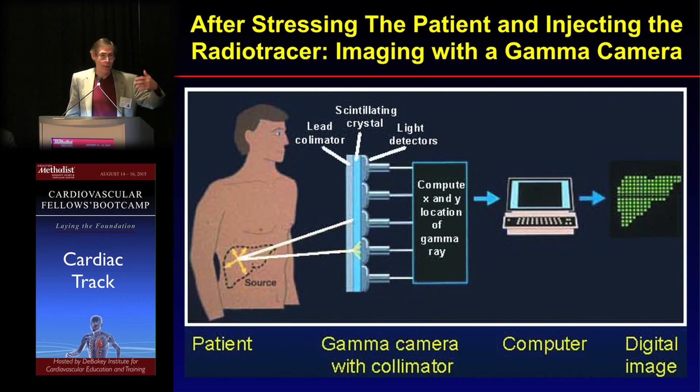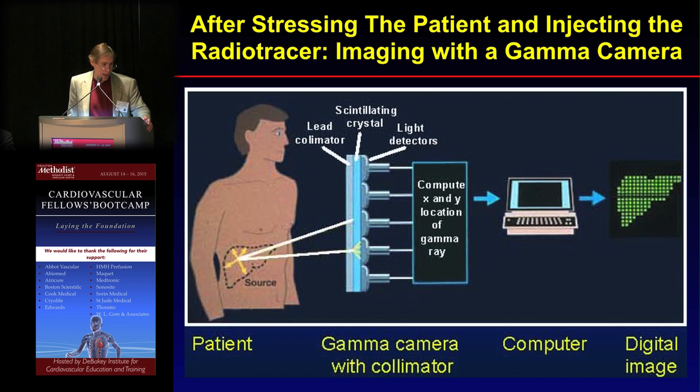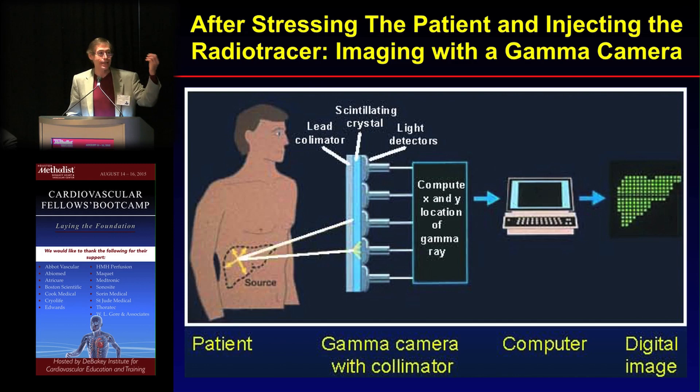Once we stress the patient and inject the radiopharmaceutical, we have to image that patient. Because gamma rays can get out of the body, they hit a lead collimator so that only photons parallel to the organ being imaged enter the sodium iodide crystal. When the photon hits the crystal, it causes a scintillation — a little bit of light.